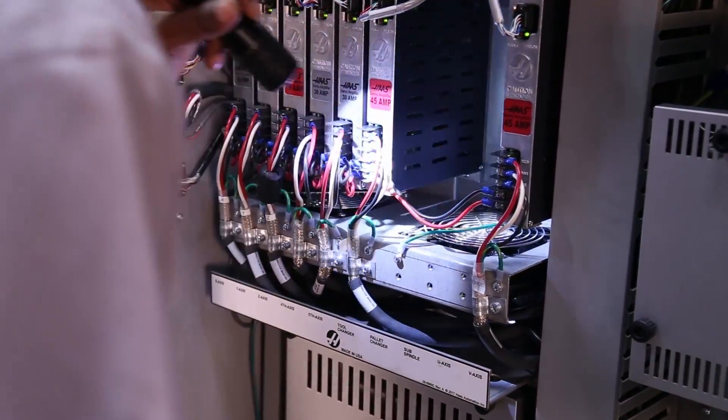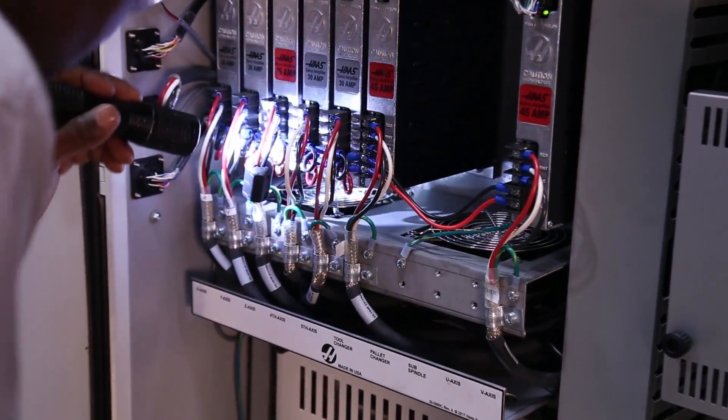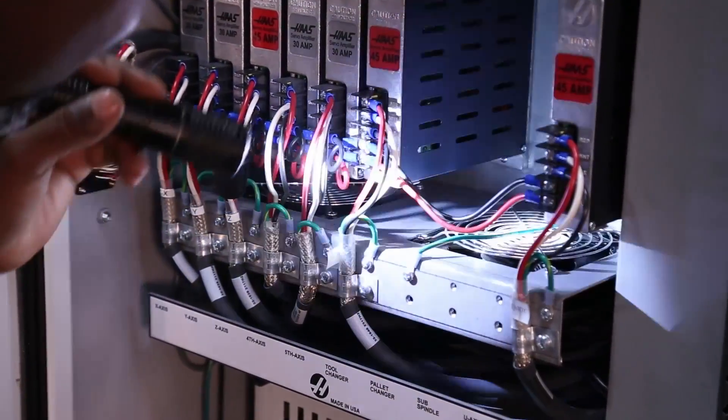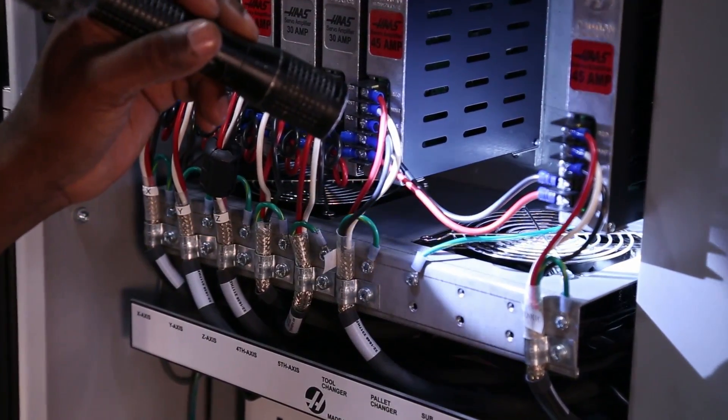Make sure the fans below the amplifiers inside the control are working correctly and that they are not obstructed.